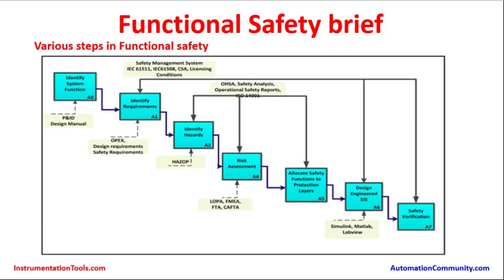How is functional safety achieved? There are many steps involved. First, identify the system with the design of the plant using P&ID and process manuals, and identify the requirements for safety, design requirements, safety recommendations, and operational excellence. Next, the hazards have to be identified using a HAZOP study. Safety analysis and operation safety reports have to be prepared based on ISO and IEC requirement standards.